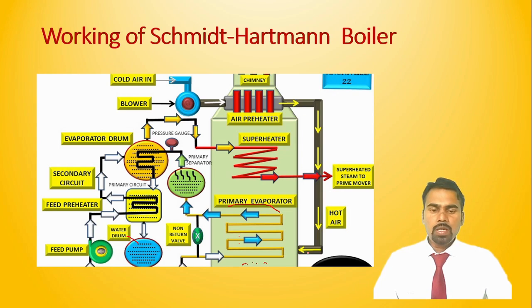Why is air preheating required? To increase the efficiency of the power plant. Because of the air preheating, the amount of fuel required to generate the heat will be less, so ultimately an increase in efficiency takes place. I hope you understood the construction, the important components of the Schmidt-Hartmann boiler. Now I will explain its working.